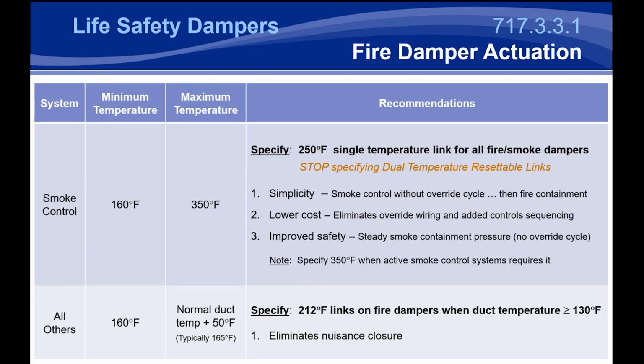Now, there was a requirement 30 years ago that you had to close all dampers within 50 degrees of ambient. To get around that, manufacturers developed a dual temperature resettable link. With that dual temperature resettable link, they had a low temperature and a high temperature that allowed the damper to be reopened after that closure point.